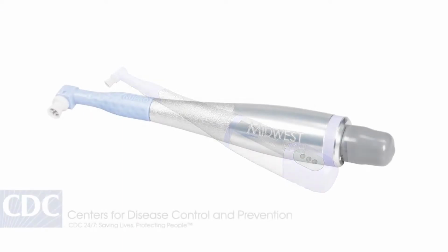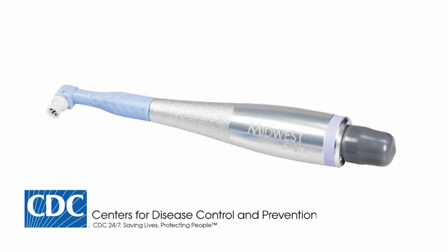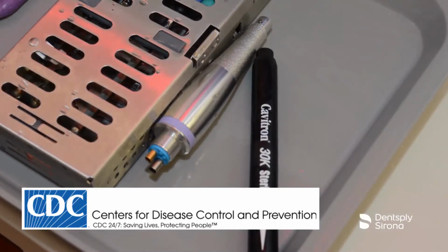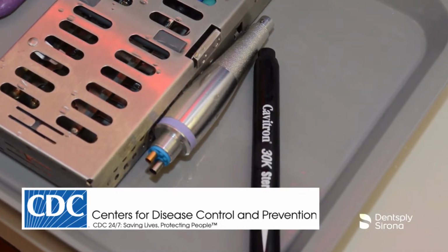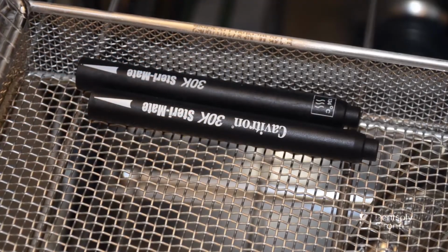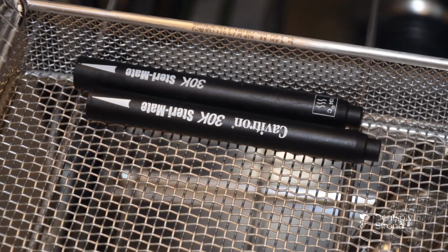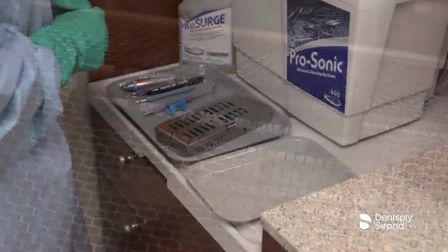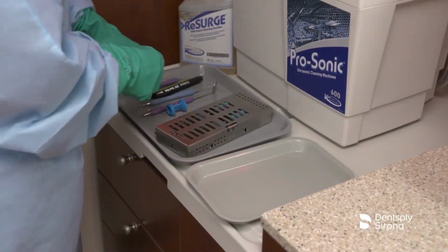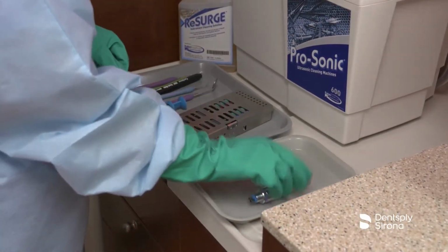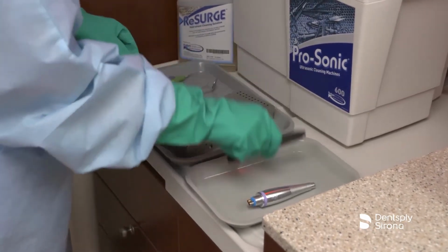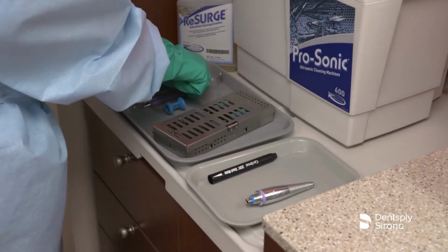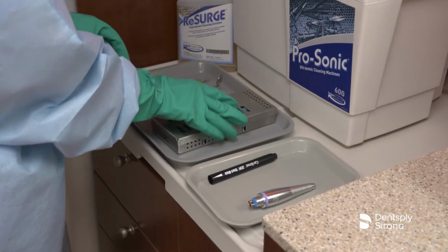The CDC's recommended guidelines for reprocessing of handpieces require heat sterilization methods to sterilize handpieces and all devices that attach to air or water lines. It is important to follow the manufacturer's recommendations for cleaning, lubrication, and sterilization of handpieces being used. Once handpieces have been separated from instruments for reprocessing and the manufacturer's guidelines have been reviewed, reprocessing should begin to prevent any residue or contamination from drying on the device.